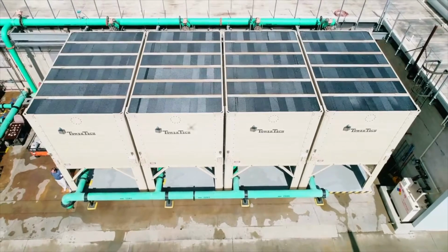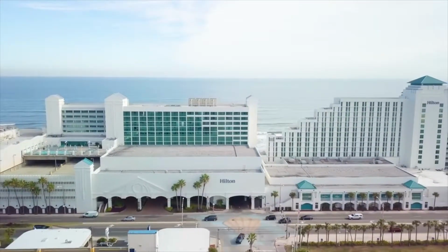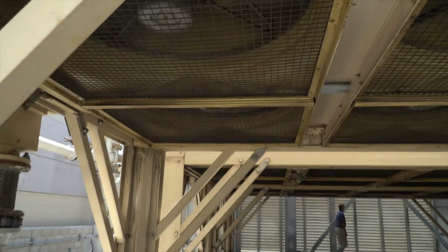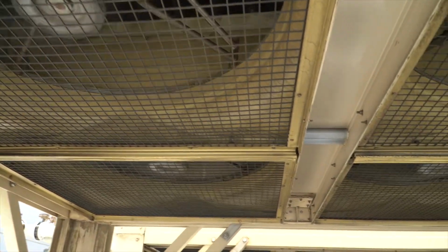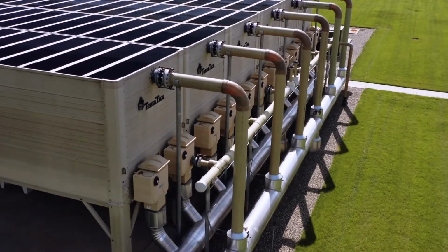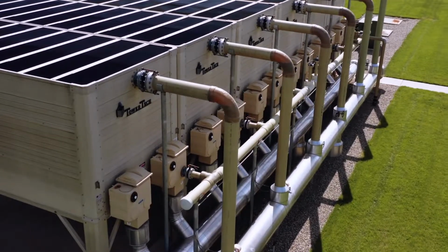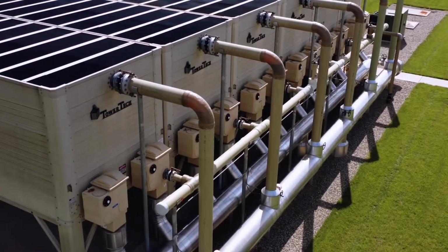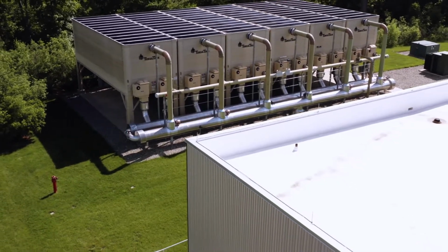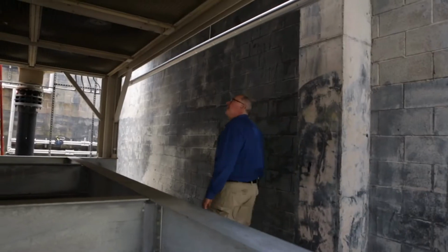The other thing I liked was the physical size, shape, and configuration. I liked the elevated tower element, the bottom-up airflow rather than the fan on top, because it allowed us the opportunity to service and maintain the equipment while standing on a concrete slab, with the tower fans 6 feet above the head of the person doing the maintenance. With taller legs you might need a step ladder, but you didn't have to crawl up on a cooling tower to service and maintain the motors.